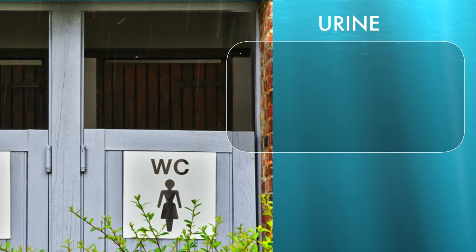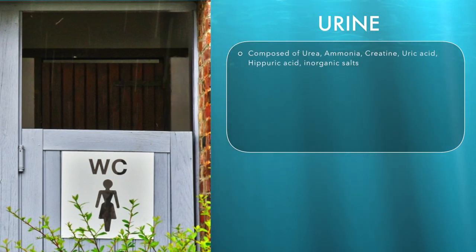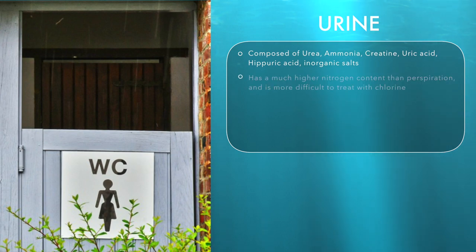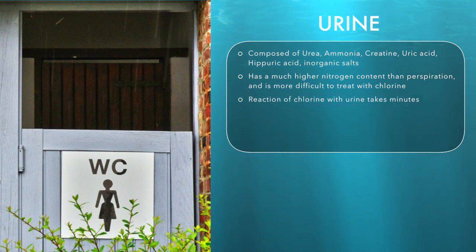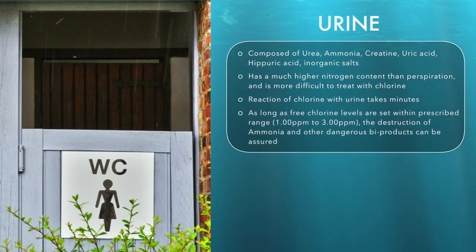Urine is composed of urea, ammonia, creatine, uric acid, hippuric acid and inorganic salts. Urine has a much higher nitrogen content than perspiration and is therefore more difficult to treat with chlorine. However, the reaction of chlorine with urine takes only minutes and as long as the free chlorine levels are set within the prescribed range — one parts per million to three parts per million — the complete destruction of ammonia and other dangerous by-products can be assured.